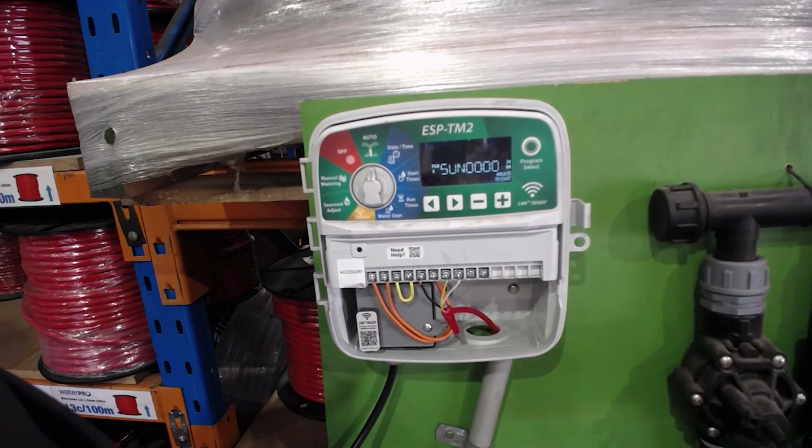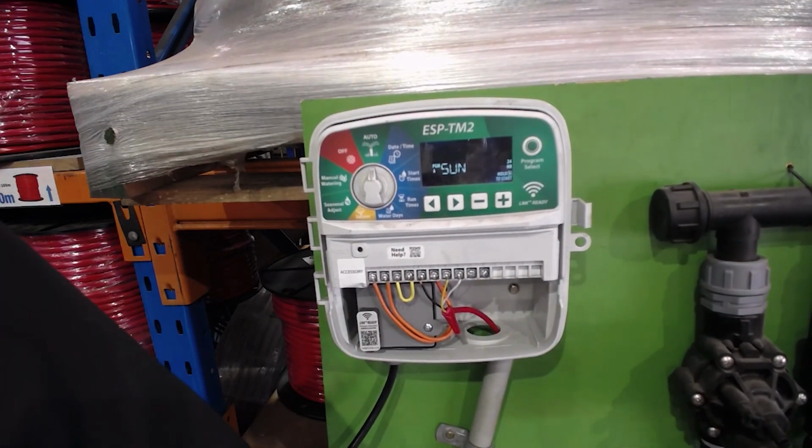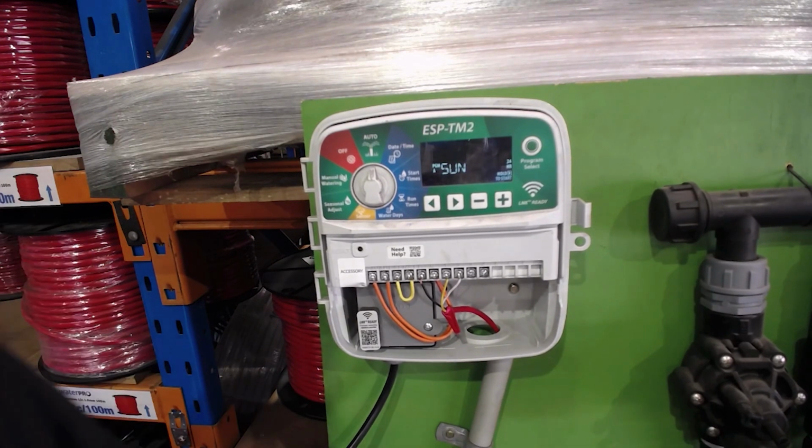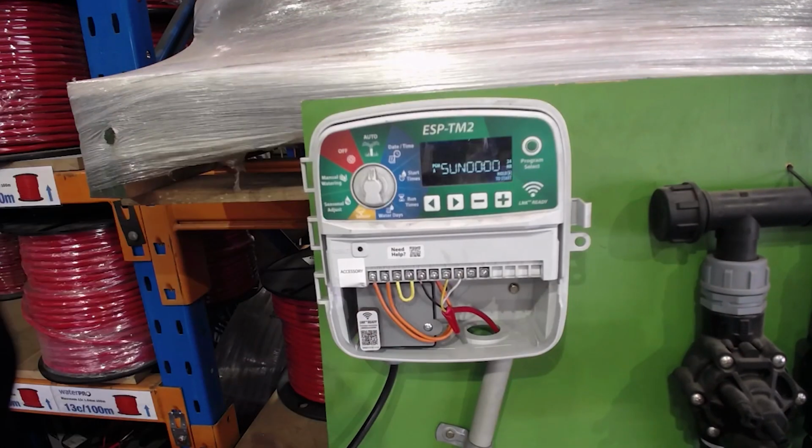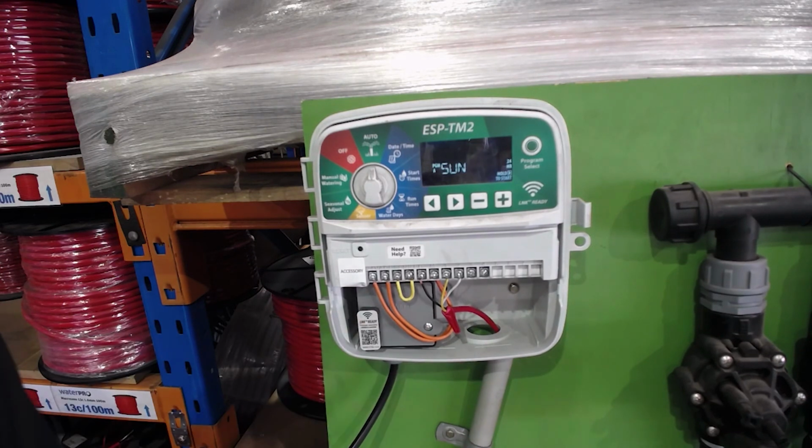And then if I did it on a Hunter coil, I'd see something like 25 ohms of resistance. Just different brands, they've got different levels of resistance. But either way, when I saw a number, I knew I've got a coil hanging off of that solenoid, which means my wires are intact, because that wire is giving me feedback that I'm actually seeing a coil on the other end.